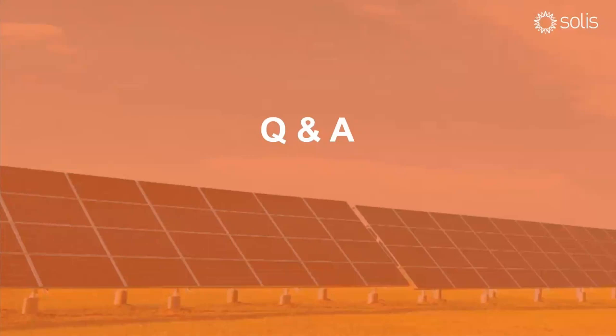I see a question from Bailey Smith about minimum kilowatt hour bank. It'll really depend on the battery manufacturer, but a general rule of thumb I've seen is 1C discharge as a maximum. So 1 kilowatt per kilowatt hour. So for example, if you had a 10 kilowatt inverter, you would want a minimum of a 10 kilowatt hour battery bank, but it really comes down to the max discharge amperage of the battery and the minimum draw from the inverter.